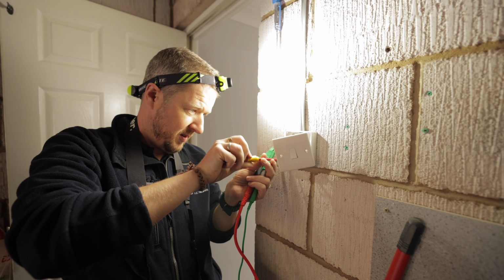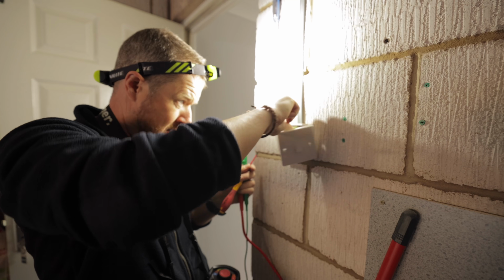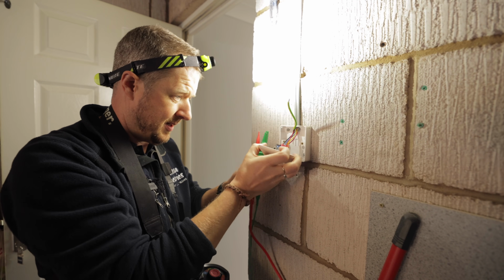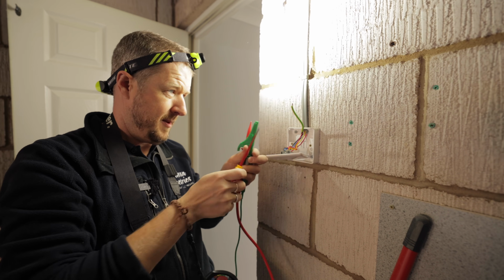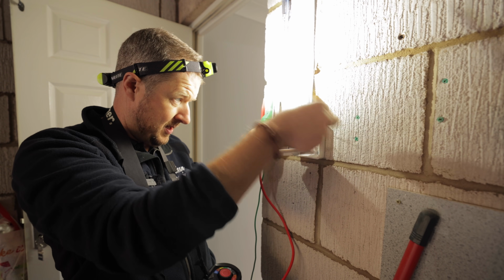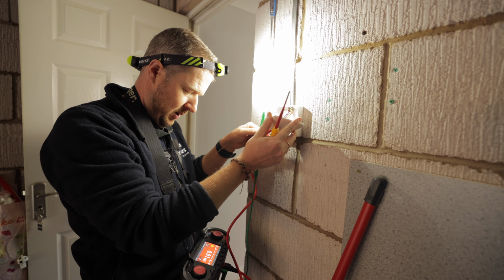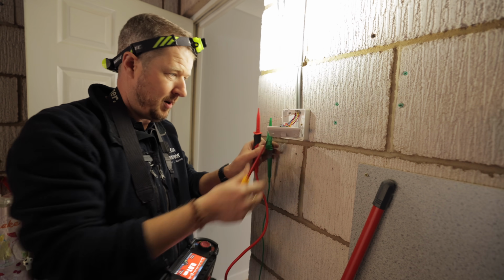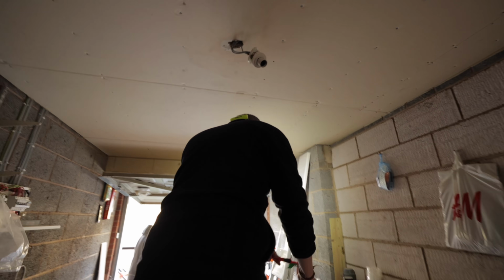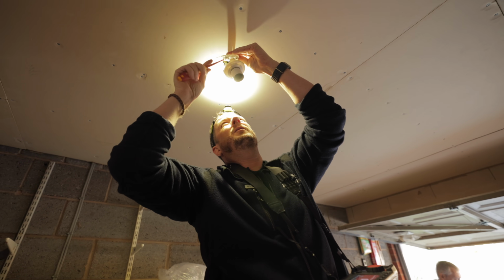So I'm getting desperate at this point, and what I'm going to do is just disconnect these wires and test individually each core. We've got a low reading there. That might just be because of the way that it's connected up here. It's usually something really obvious, guys. That's the thing with fault finding.